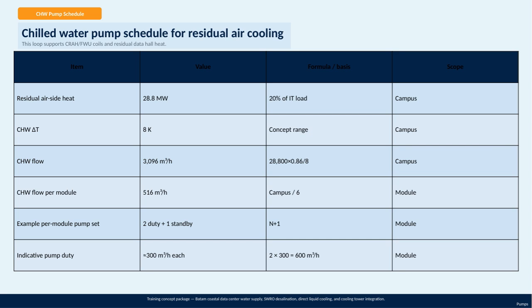The chilled water temperature differential, or delta T, is set at 8 Kelvin, falling within the conceptual design range for the campus. To handle this, the total chilled water flow required is calculated to be approximately 3,096 cubic meters per hour. When we break this down per module, assuming 6 modules of the campus, each module requires around 516 cubic meters per hour of chilled water flow.